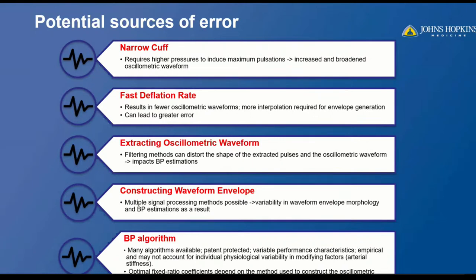In addition, blood pressure devices often have a fast deflation rate because end users prefer it—it gives a quicker measurement. But with that fast deflation rate, you get fewer oscillometric waveforms, so the device has to interpolate more to generate the envelope, which can lead to greater error.